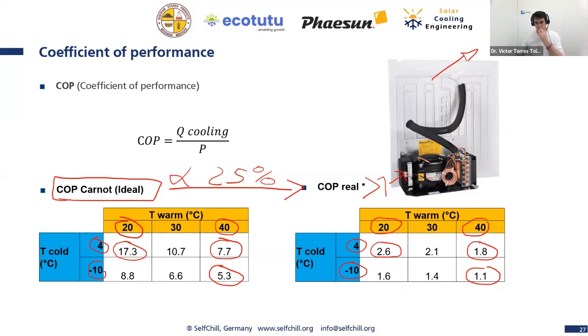The reason is that the cooling energy is coming from the ambient. The hot ambient is providing the cooling energy that can be delivered at the evaporator, and the energy of the compressor is just helping us to transport this energy, to pump this energy. So let's repeat this question again. Please vote again, if you are still not convinced. Yeah, it's free lunch, isn't it?